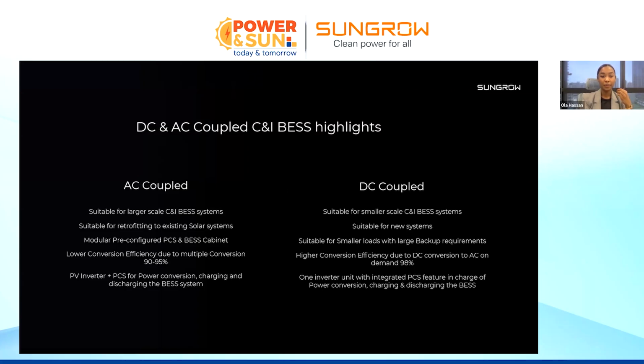It has lower conversion efficiency, all right. Here's the typo: it has lower conversion efficiency, higher losses due to multiple conversions. Because what's happening right now with the AC coupled? Our PV is giving us DC power. Our inverter is converting this DC power to AC. Again, this power is going to the PCS. Our PCS is converting this power to DC to store and charge the batteries. And then after that, if we need the AC power, then again it's converted to AC and injected at the point of connection. So we can have multiple conversions of power.